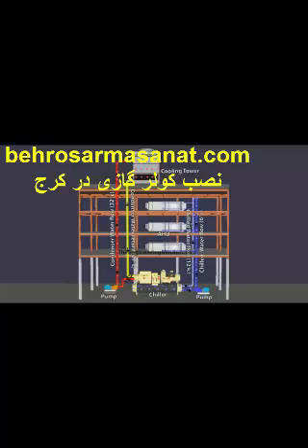It's returning here at about 12 degrees. By the time it leaves the chiller again, it will have given up 6 degrees Celsius worth of heat, so it's leaving at 6 again. So it leaves at 6, comes back at 12, and this cycle repeats and repeats.